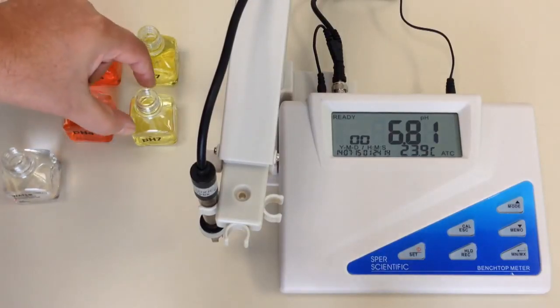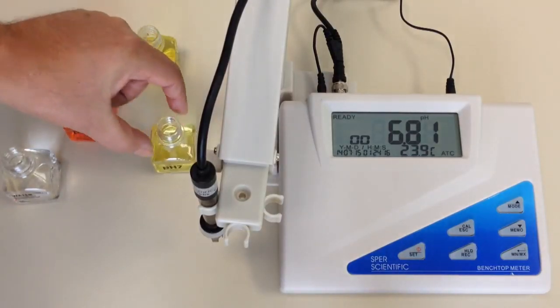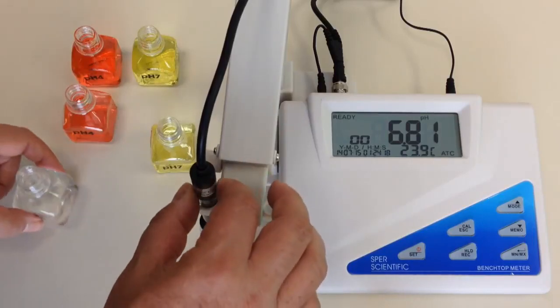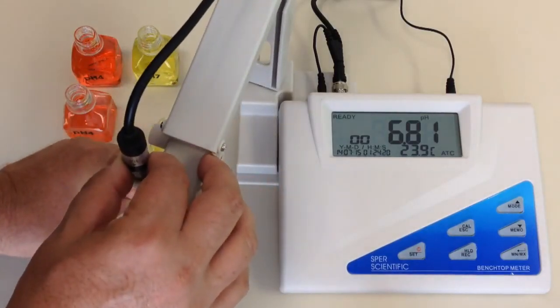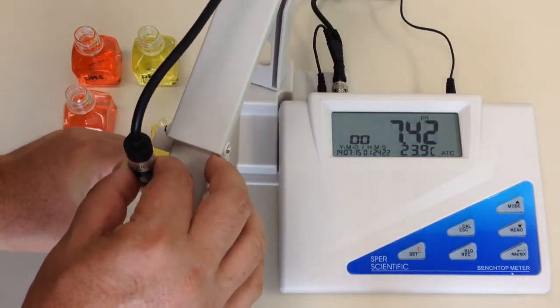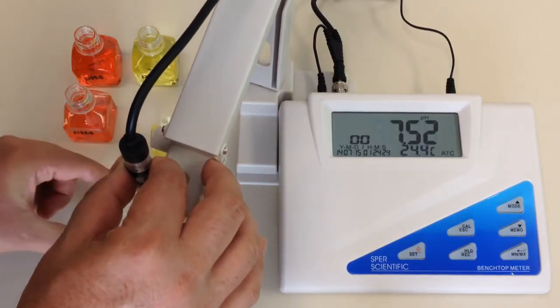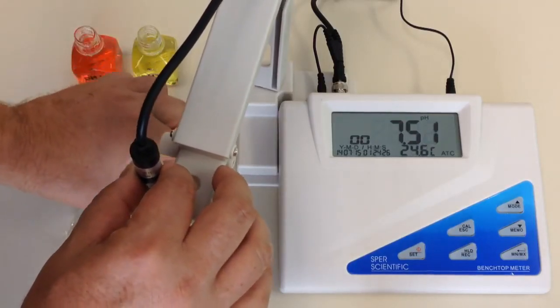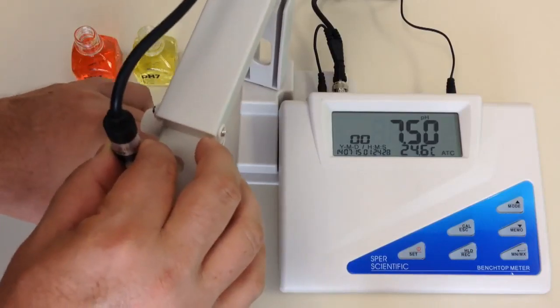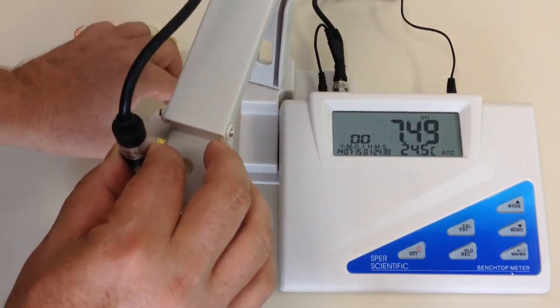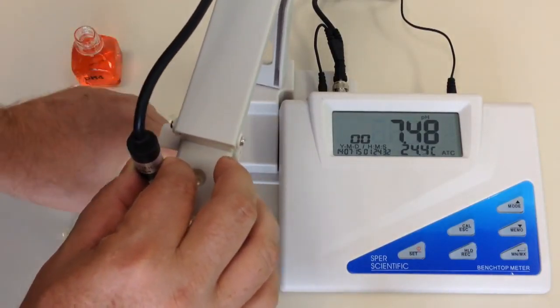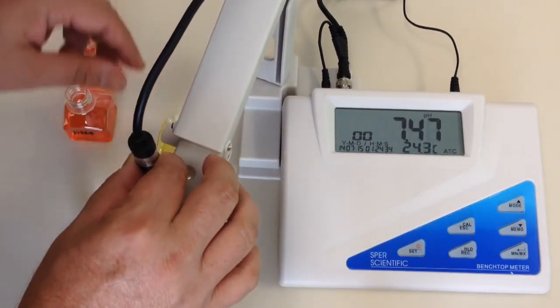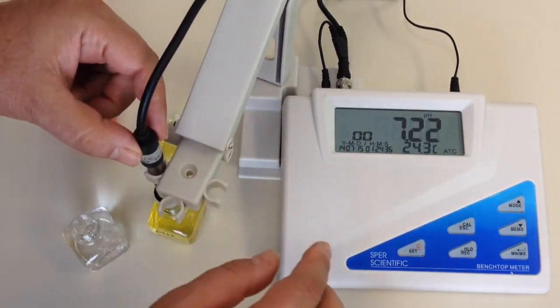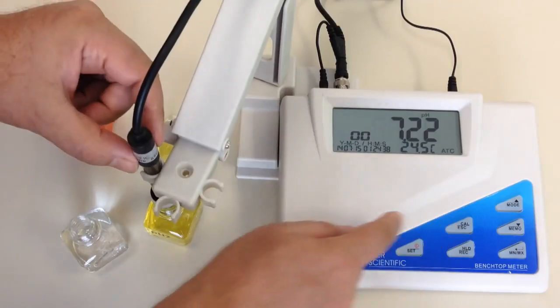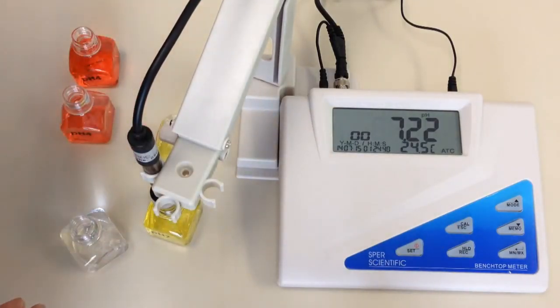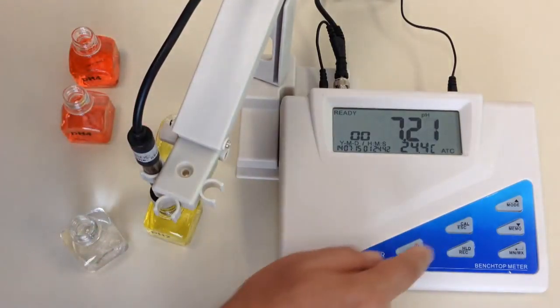In this case, I'm going to be calibrating first to pH 7. So we're using best practices. I'm going to first clean my probe by dipping it into a little bit of distilled water. Then I'm going to put it into my first buffer solution, and so that I don't contaminate what I'm actually going to be using, I'm going to then put it into this one. Now I'm ready to calibrate the meter. So you can tell that the probe is fully inside my solution.